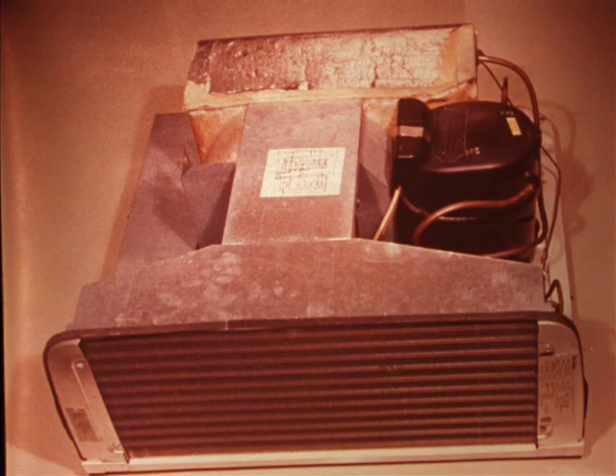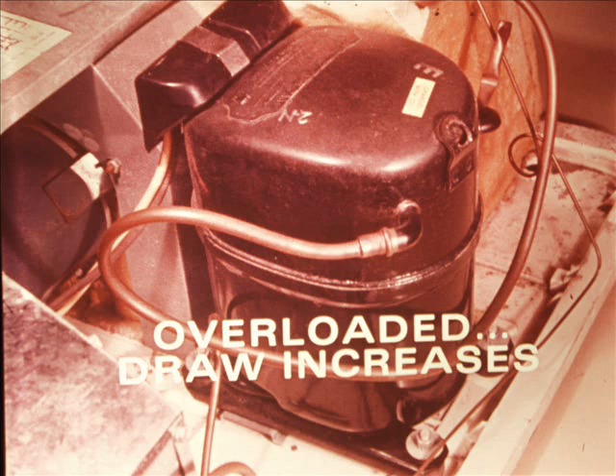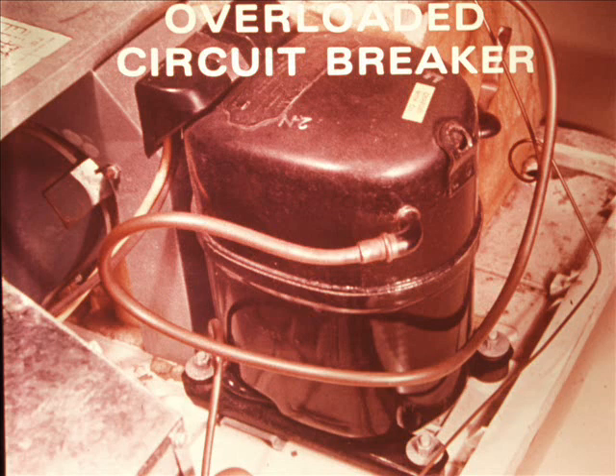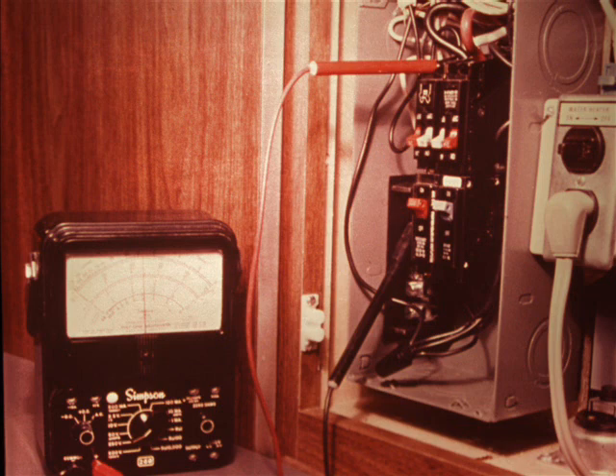With roof air conditioning, low voltage can cause on-off operation and can destroy the compressor motor. A compressor motor that has too little voltage available will strain to operate on the low voltage. In other words, it becomes overloaded and current draw increases. The overloaded circuit breaker may protect the motor initially by opening the circuit. However, it resets when it cools and the motor strains to run again. If the compressor motor is still okay when you get it, check the unit with a known good 120 volt source to see if low voltage is the only problem.